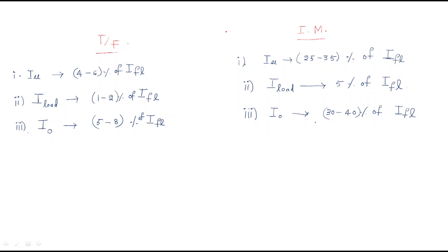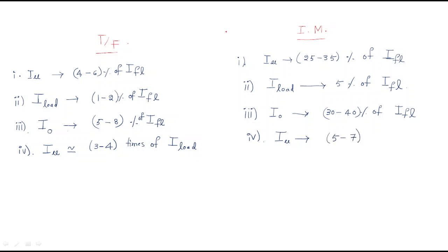The fourth point gives the relation between magnetizing current and load current. For the transformer, the magnetizing current is approximately 3 to 4 times the load current. For the induction motor, the magnetizing current is 5 to 7 times the load current — the magnetizing current is heavily dominant.